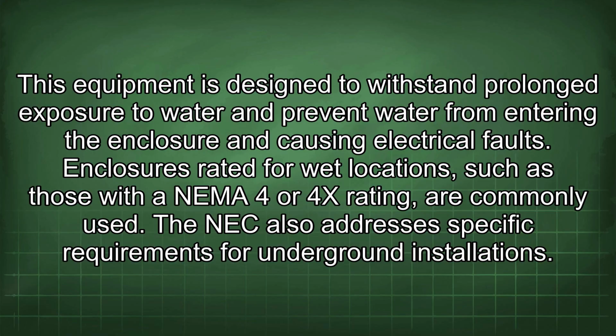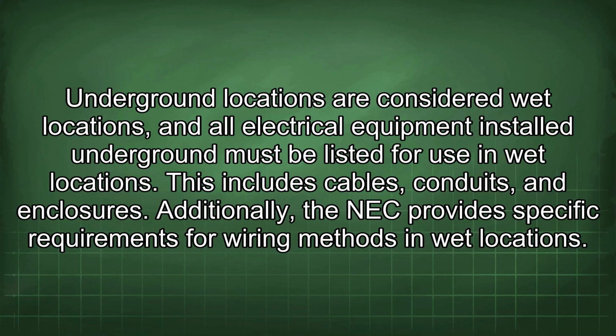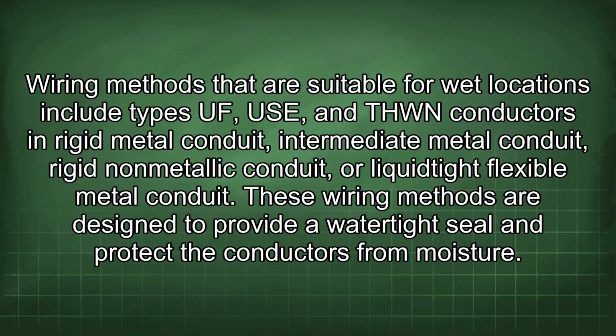The NEC also addresses specific requirements for underground installations. Underground locations are considered wet locations, and all electrical equipment installed underground must be listed for use in wet locations. This includes cables, conduits, and enclosures. Additionally, the NEC provides specific requirements for wiring methods in wet locations. Wiring methods that are suitable for wet locations include types UF, USE, and THWN conductors in rigid metal conduit, intermediate metal conduit, rigid non-metallic conduit, or liquidtight flexible metal conduit. These wiring methods are designed to provide a watertight seal and protect the conductors from moisture.